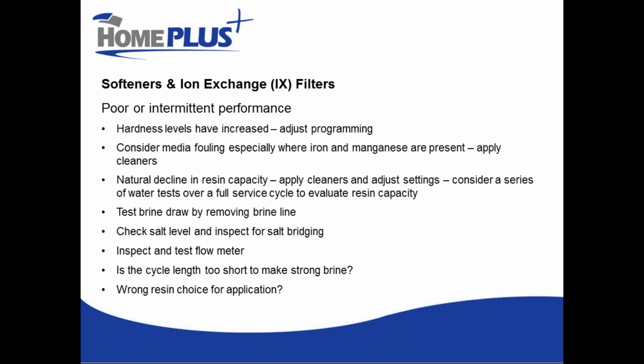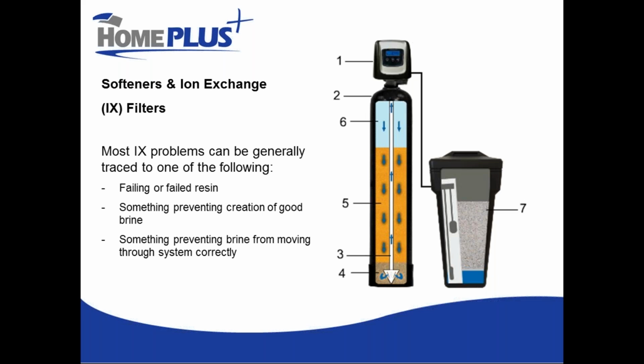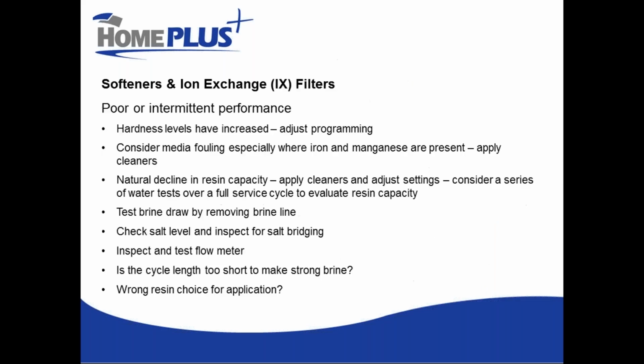A couple of other quick inspections to do: clean your brine tank components. At the bottom of that gray tube at the bottom of the brine tank, there's a little check ball. It's really important that that check ball be moving and not be stuck, so make sure it's operating correctly. Check that the safety float is operating correctly. Make sure the salt is actually falling all the way down to the bottom of the tank. We sometimes see what we refer to as salt bridging, which, like its name suggests, is a bridge of salt at the top of the brine tank with a big hollow cavity underneath, preventing the salt from actually touching the water at the bottom of the brine tank.